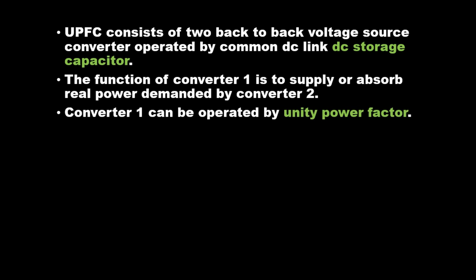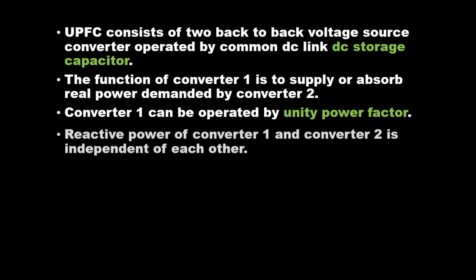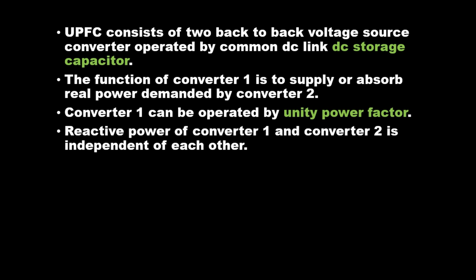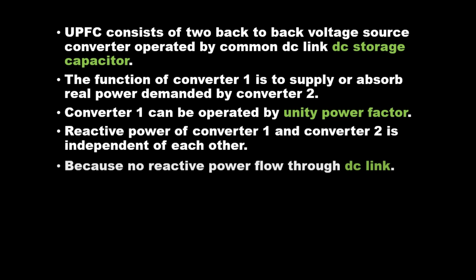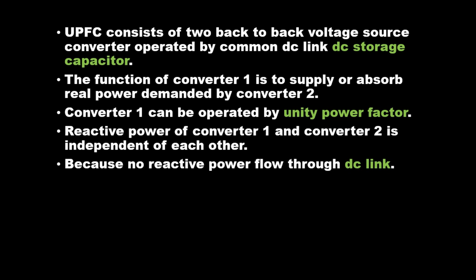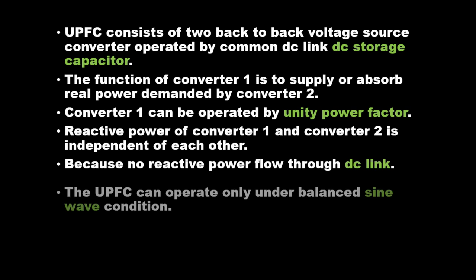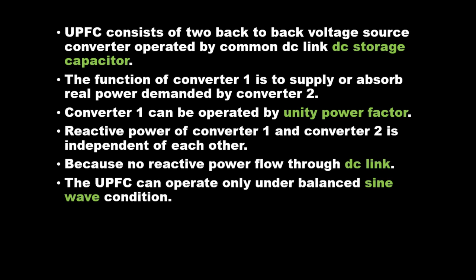Converter 1 can be operated at unity power factor. Reactive power of converter 1 and converter 2 is independent of each other, because no reactive power flows through the DC link. UPFC can operate only under balanced sine wave condition.